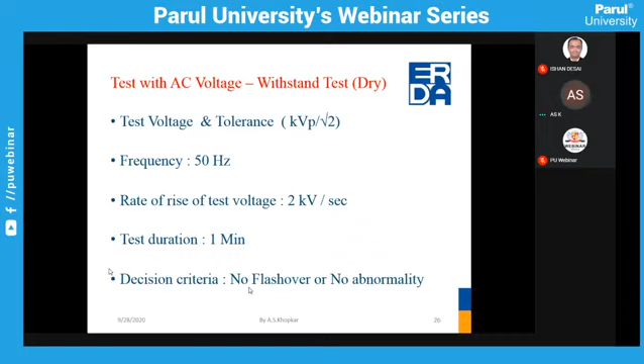Similarly, for the flashover test in AC power frequency, again the voltage measurement is kV peak by root 2, the frequency is 50 Hz, and the rate of rise we keep is 2 kV per second. But here the flashover value is to be determined, meaning we slowly increase the voltage till the flashover or disruptive discharge occurs, and that value has to be recorded, and that is called the flashover value. This test is particularly applicable on insulators only, because in the case of insulators, people want to know the maximum withstand capability, or what the flashover value is.